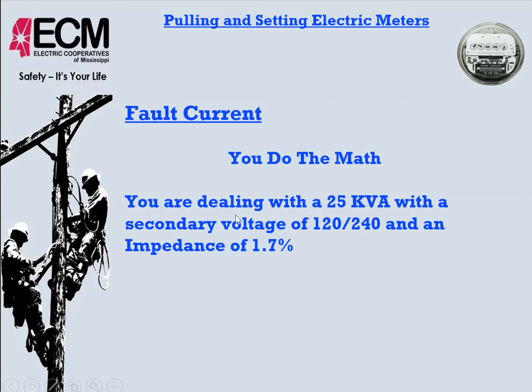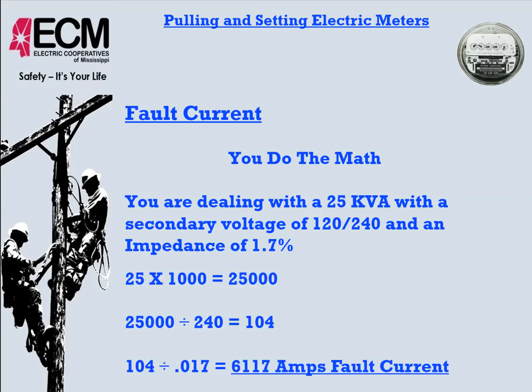Some ideal situations that we typically would run up on would be a 25 kVA transformer, secondary voltage of 120-240, and an impedance of 1.7%. Notice that that is a percentage, so in multiplication we will want to move the decimal 2 places, so we're going to use 0.017 in our calculation. And this is what that looks like. You take the 25 kVA, multiply it times 1,000, gives us 25,000. Then you take the 25,000 and divide it by the phase-to-phase voltage, 240, and that 25 kVA transformer can deliver 104 amps.